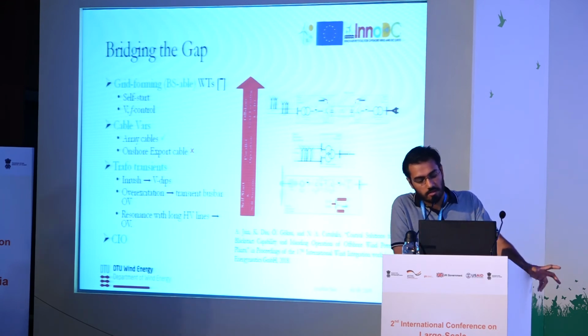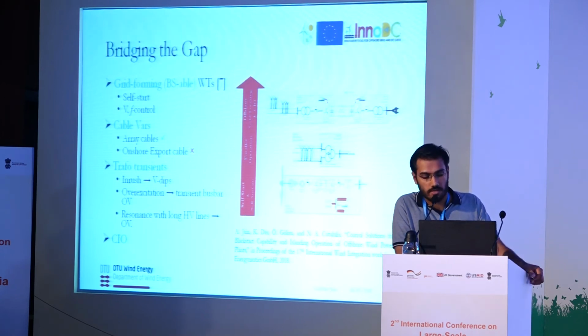Summarizing, the main important requirement is grid forming or Blackstartable wind turbines, because this can help build the local voltage and frequency and the collector grid, and also power up or energize the auxiliaries and the cables. Right now, offshore wind turbines, the large ones, can deal with the megavars of array cables. However, the export cable energization is a bit far from technological readiness. And then ultimately dealing with transients in a controlled manner, especially the large transformer inrush currents, resonance issues in the HVDC link needs to be studied, and a controlled islanded operation has to be guaranteed before a wind farm can provide a power system restoration service to the onshore operator.